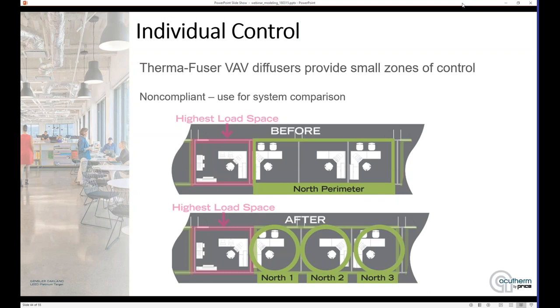Bringing this into a model means creating what's known as a noncompliant run. Part of the ASHRAE standard says that to do an energy model comparison, the zoning must be the same between the baseline and the model building. However, because a Thermafuser diffuser system does provide additional zoning, you can run this noncompliant model — nothing's saying you can't run the model with different zoning between the model building and the baseline. It just becomes known as a noncompliant run. It means you can't use it for something like LEED, but you can use it to see the results and what the energy savings are. Those can be presented to building owners interested in what their real savings are, so it's still a valuable tool within the modeling.